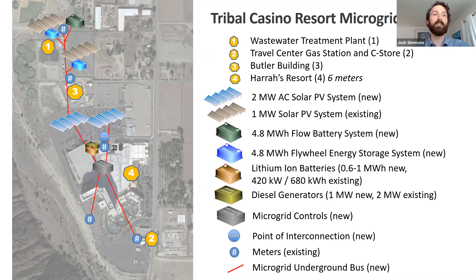They're not turning off slot machines, they're not turning off the HVAC system. We're sizing it so it's a 15-minute lithium ion battery that can handle a huge load at once, then allow the flywheel and flow batteries to kick in for ongoing outage capacity that gets them through a day or more, storing the solar energy added on site as well. So this is one use case scenario combining energy storage technologies.